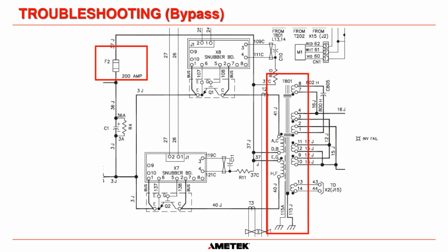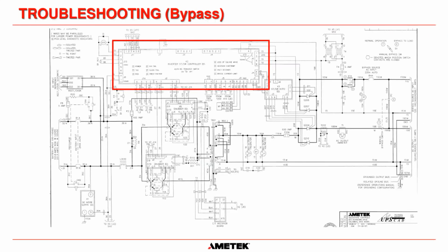Okay, so it's very difficult to tell if that happened. You have to disconnect 16 and 10 and disconnect many portions of the transformer, and then try and just get the main windings and look at them down to ground. And if you have a short, then you do have to replace the transformer. And of course, the last thing, if it's transferred to bypass, is it could be there's something wrong with the inverter static switch control board. And, you know, this is not the time or place to try and say why you would do that or what you would do that. It's just one of those things. If you've checked everything else and none of those things are bad, then it could be that the X2 board has failed.